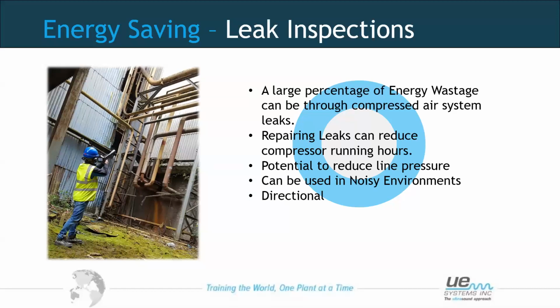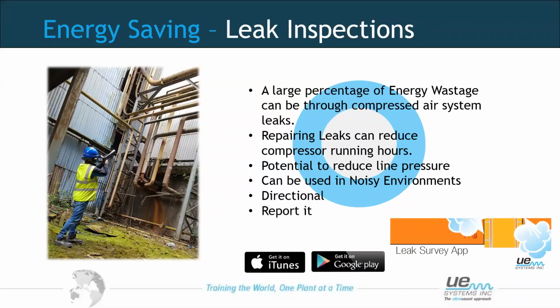We can use ultrasound in noisy environments to detect our leaks. Most plants will be noisy. That's audible sound, so again, we're listening for the ultrasound, the directional sound. And ultrasound heightens our senses. It helps us understand. An air leak in the ultrasonic spectrum will sound like an air leak audibly to you. So we can pinpoint these areas very quickly, very easily. With ultrasound technology, we can identify the leaks, we can pinpoint the location, and we can quantify them using reporting formats, either with the software that comes included with the equipment or via leak apps.